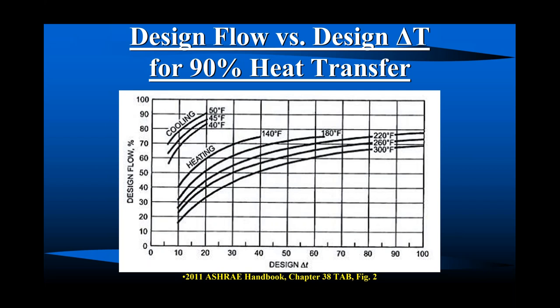So our heating system temperatures that we've used for many decades, the 180 to 160, 20 degree delta T. So there's our 20 degree delta T, and if we go up to 180, what design flow do we need to get 90% of the heat transfer out of that terminal unit? 50%. So if we needed 10 GPM, that's my design day flow to get the BTUs per hour out of that heating coil. If I only send 5 to it, 90% of the time it works well.